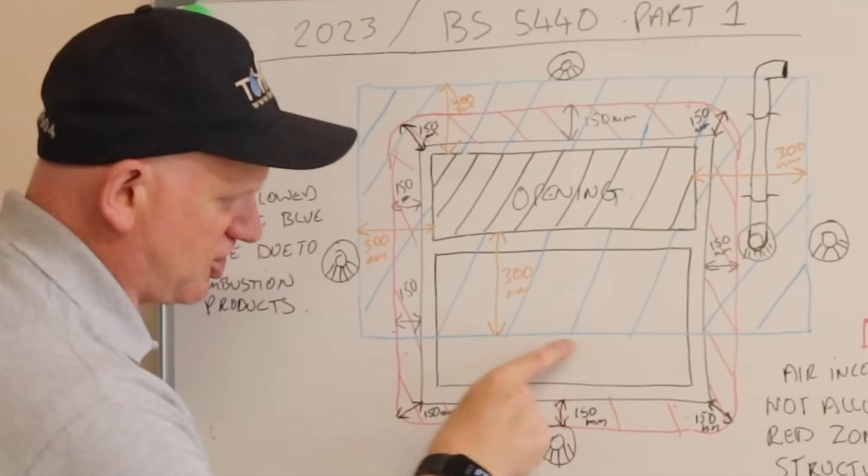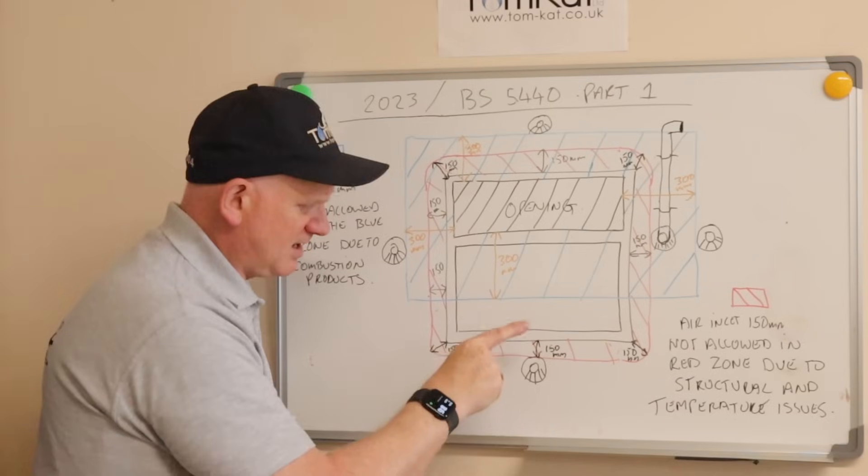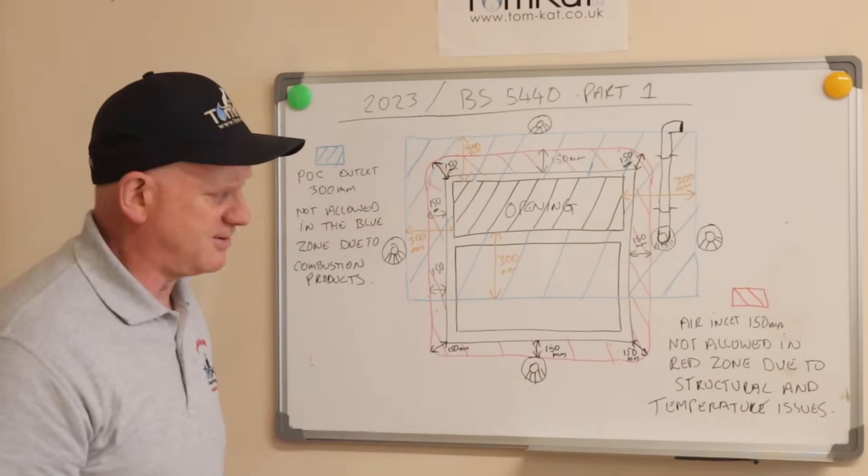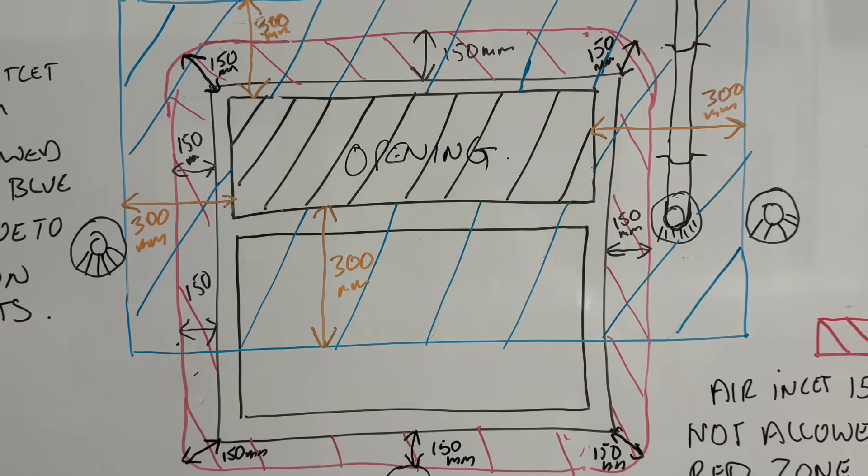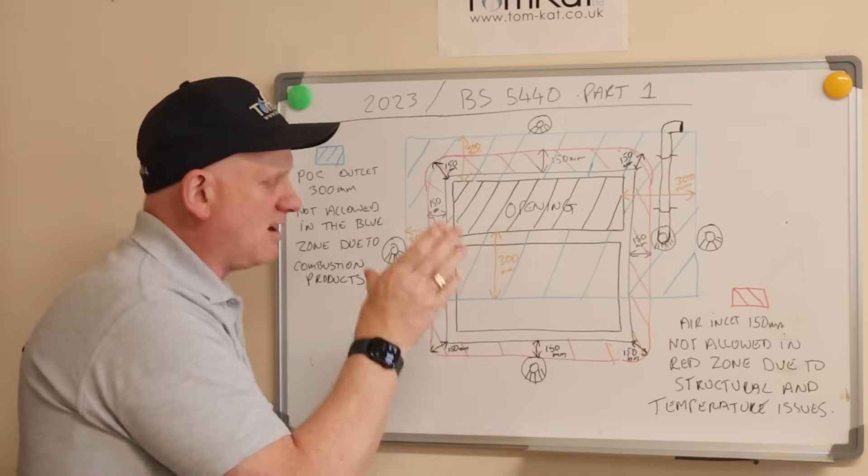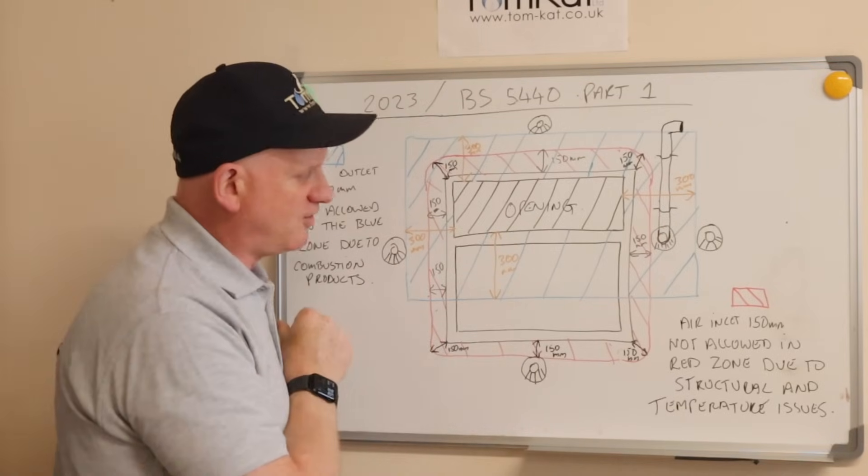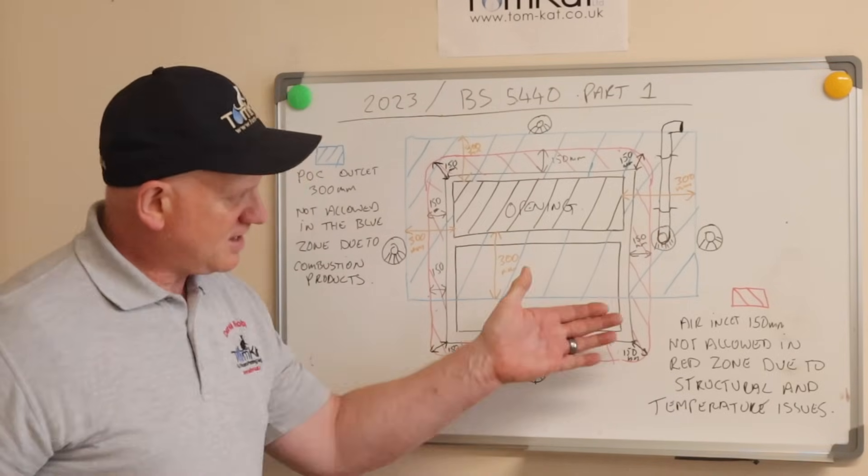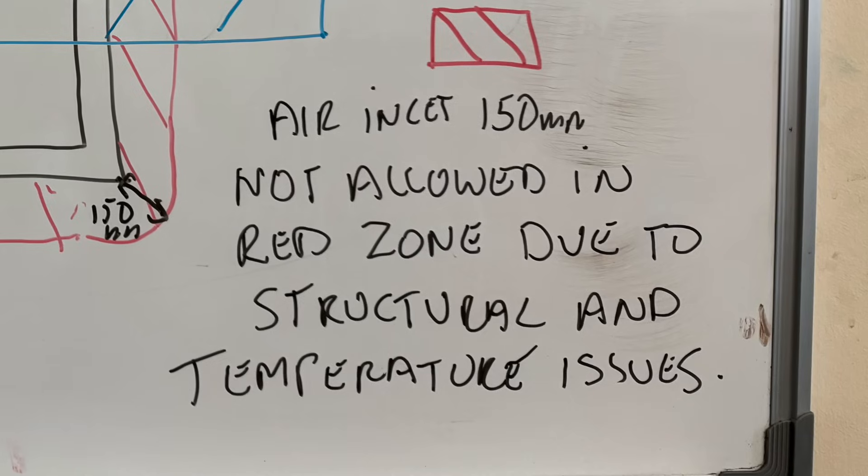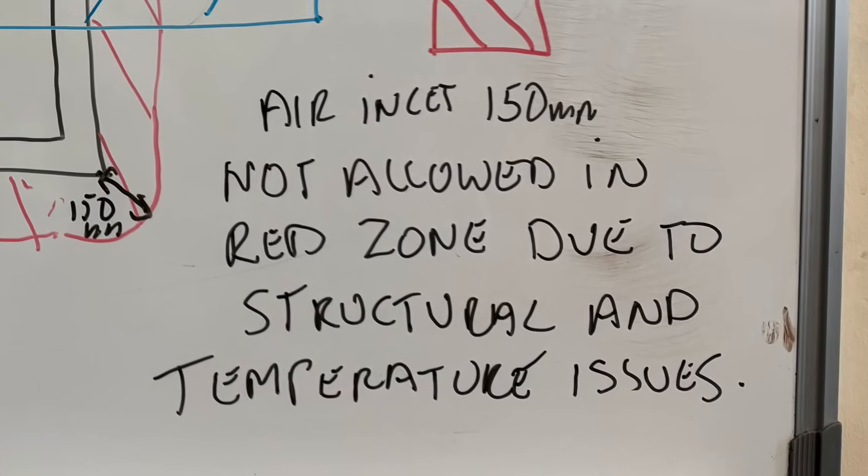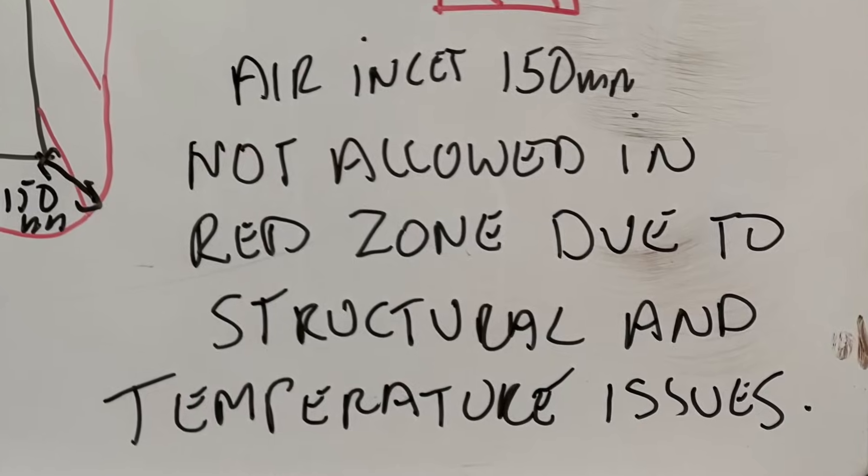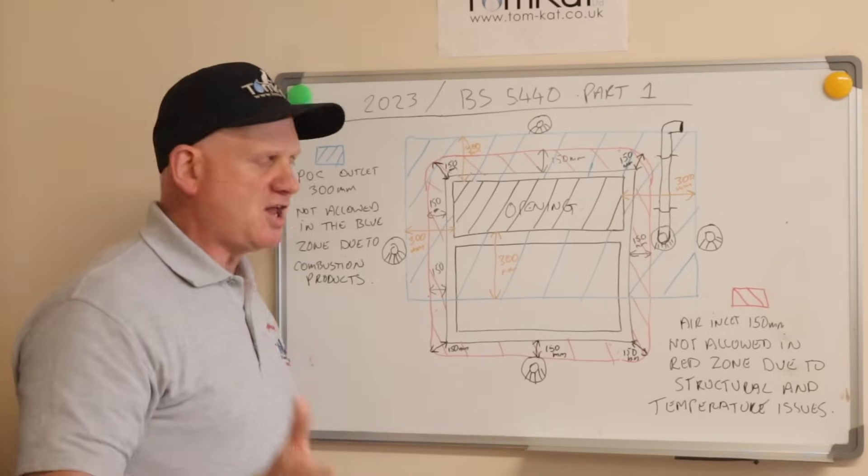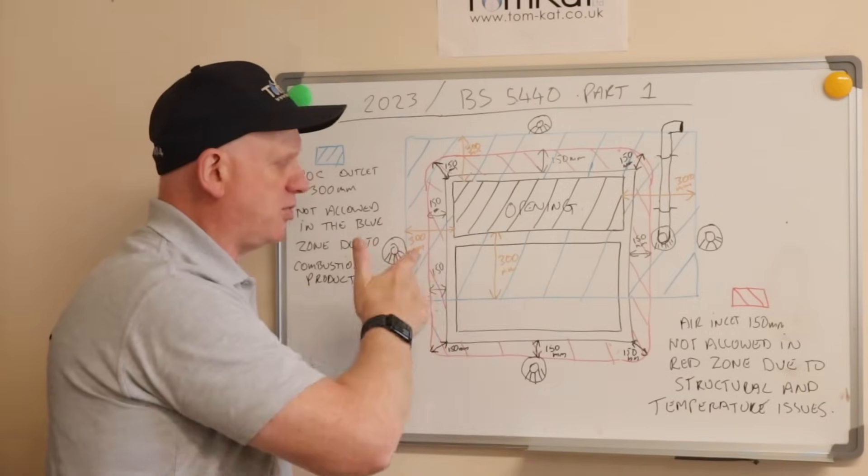So technically you can install the flue anywhere outside the shaded blue zone. Obviously you wouldn't be installing it here, but it means you could install it below the window. Now the red section you can see here is 150mm away from the frame.